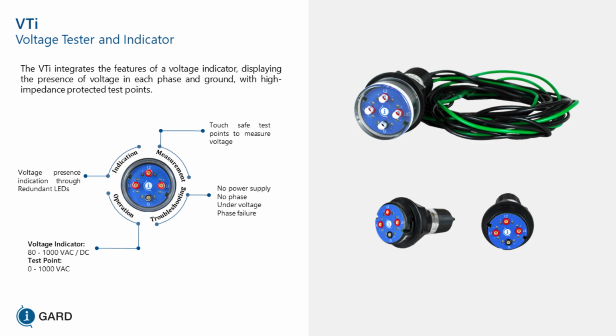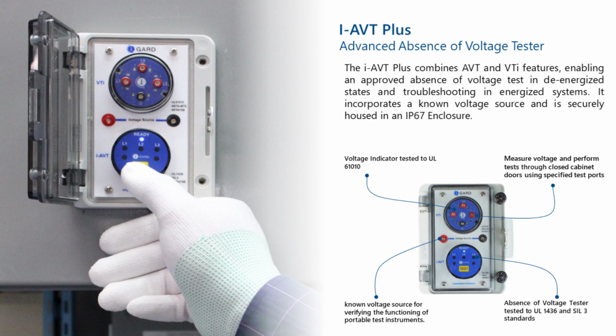No power supply, so it's not really a unit that requires power other than the voltage on the bus. It's up to 1,000 volts AC, category 4, and the test points are 0 to 1,000 volts. So you can measure the voltage on the bus, and the indicating lights go up to 1,000 volts. And we have the IAVT Plus. This is both units combined, with the VTI on the top and the IAVT on the bottom.